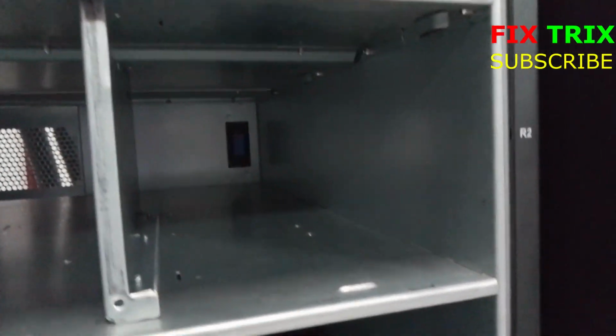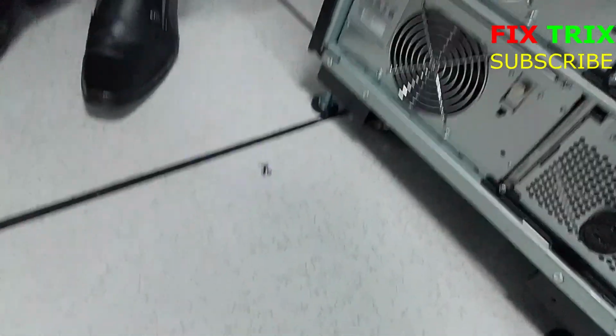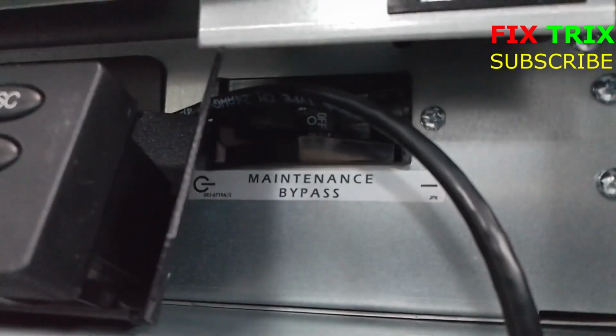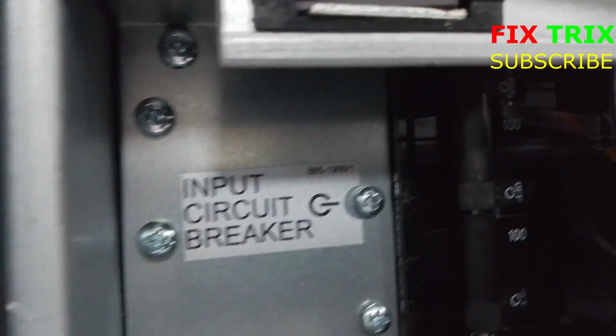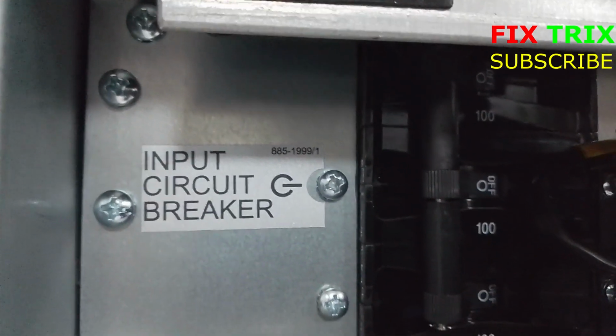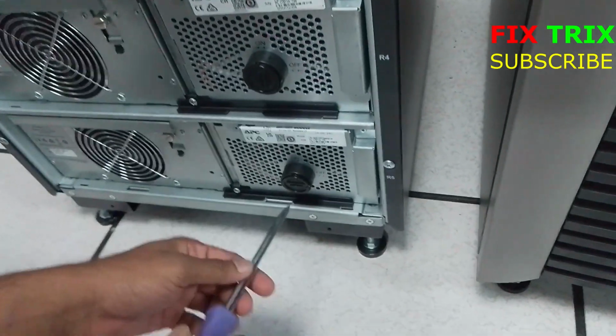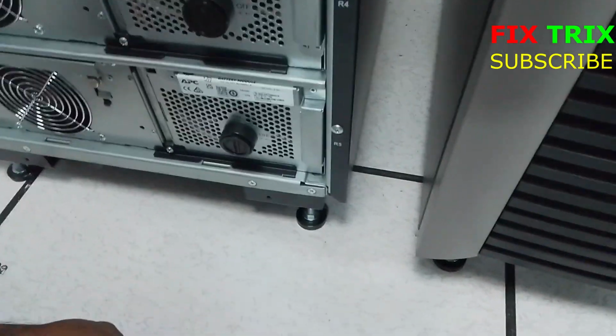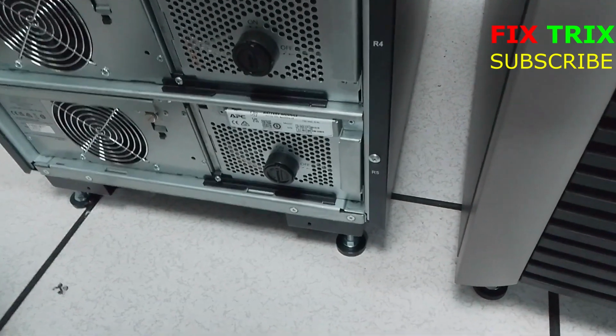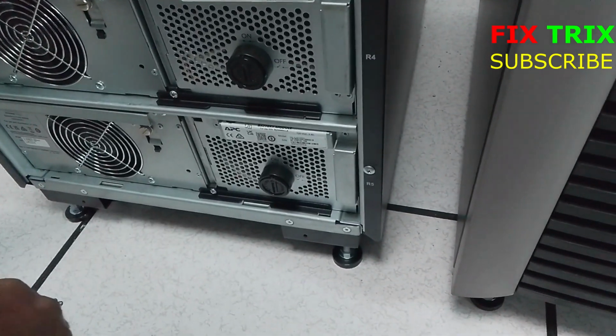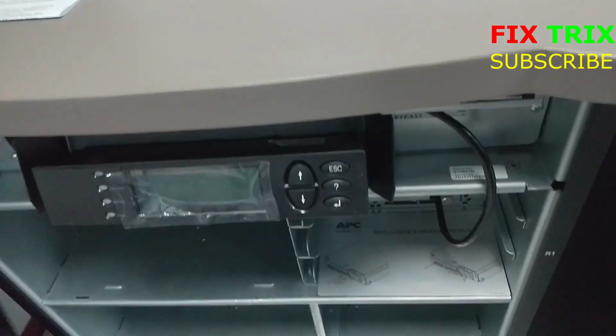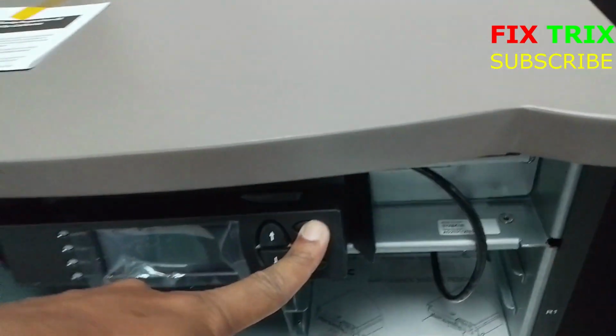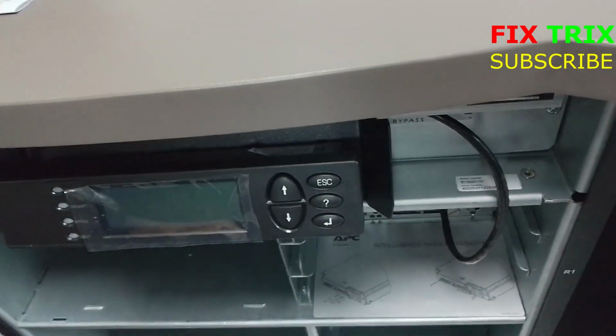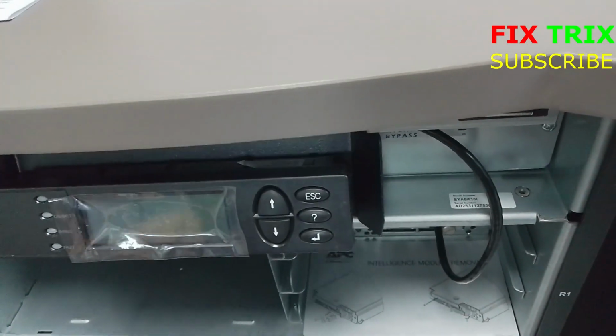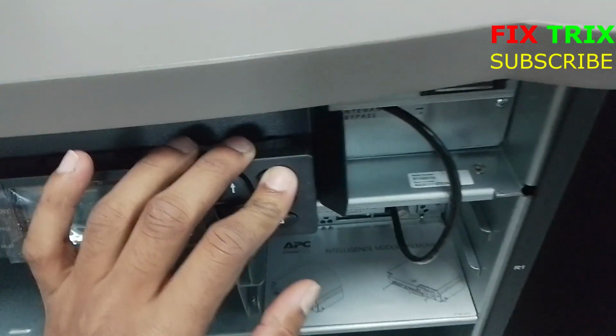Here you can see the maintenance bypass switch. This switch is used to bypass the UPS internally. When we turn on the maintenance bypass, utility power goes directly to the load, and you can see the input circuit breaker. This breaker controls the main utility power coming into the UPS. When the input circuit breaker is on, utility power enters the UPS and we turn on the battery modules. On each battery module you can see a battery on off switch. Now we move the switch to the on position.